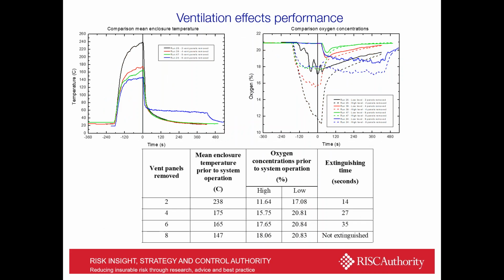Ventilation, another key feature for systems such as this. We can see that they're inherently linked in their ability to put out fires to the oxygen content of the enclosure and how they can drive it down. So here we have, if you can remember the schematic before, where I've removed a series of door panels, 2, 4, 6, and 8. And what that changes between these tests is not only the temperature of the enclosure, because the fire burns less efficiently. We can see that in the left-hand graph, actually, this is more about holding on to heat, with the highest temperatures for the least panels removed. But you can see, more importantly, on the right-hand graph, the residual oxygen concentration within the compartment for the different ventilation levels. And as we remove panels, or increase the ventilation of the compartment, you can see the extinguishing time increase from 14 to 27 to 35 seconds, to the point when 8 panels are removed, it doesn't extinguish at all.